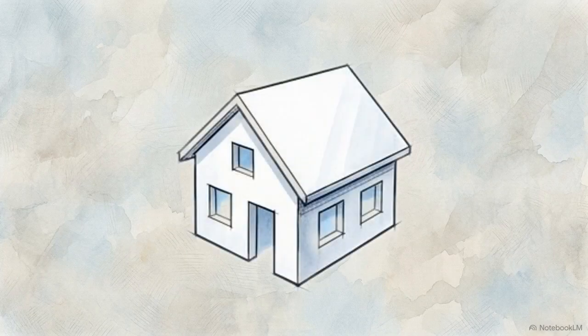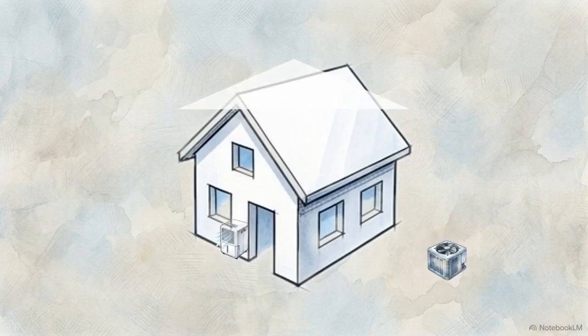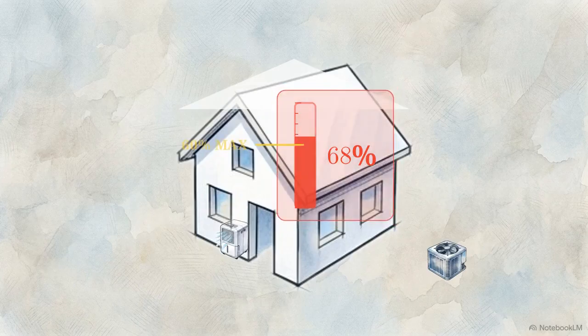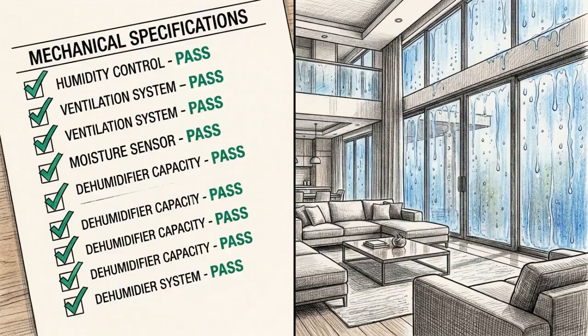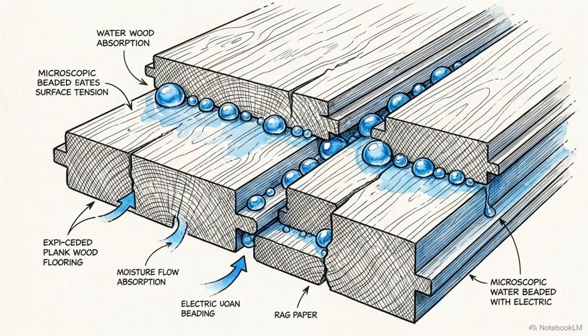But this diagram shows a scenario we see consistently in South Florida. Even with a sealed attic and properly sized equipment, the relative humidity in the living space remains stubbornly trapped. It refuses to drop below 60%. Standard mechanical solutions, while technically correct on paper, often fail to control the environment in these high water table settings. The humidity persists despite every conventional safeguard.